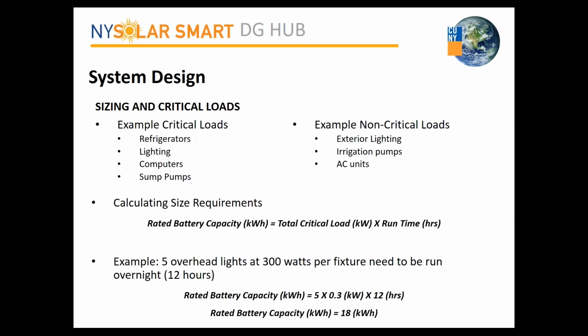This also goes back to the objectives of the project. Maybe refrigeration is a really high priority for the facility, or in some cases it could be a non-critical load if the primary objective is just to keep the lights on and maybe a couple of computers. But going through these different loads, figuring out what's critical and what's not, and once you've nailed down that list, you calculate what size requirement the battery is going to have.